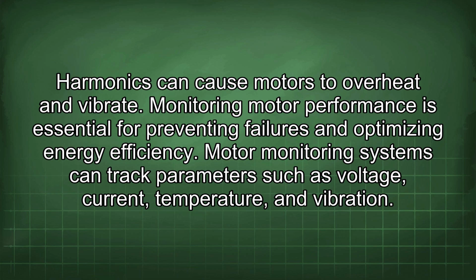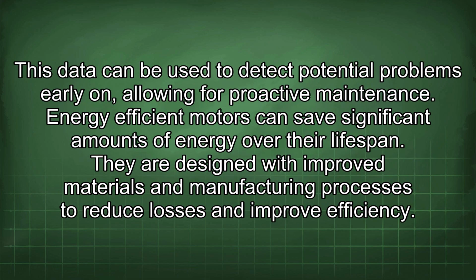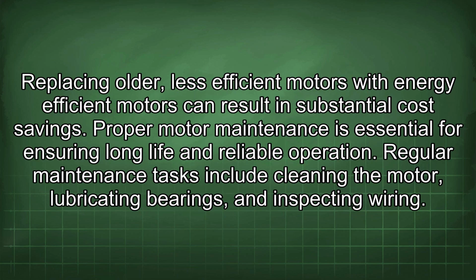Monitoring motor performance is essential for preventing failures and optimizing energy efficiency. Motor monitoring systems can track parameters such as voltage, current, temperature, and vibration. This data can be used to detect potential problems early on, allowing for proactive maintenance. Energy-efficient motors can save significant amounts of energy over their lifespan. They are designed with improved materials and manufacturing processes to reduce losses and improve efficiency. Replacing older, less efficient motors with energy-efficient motors can result in substantial cost savings.